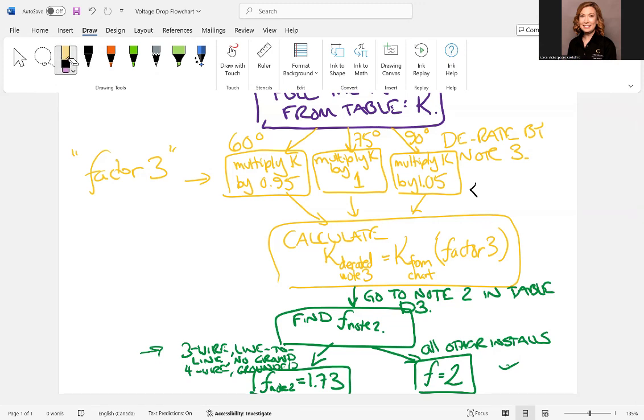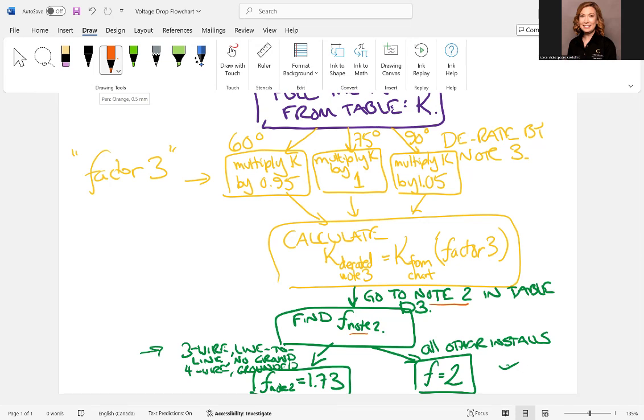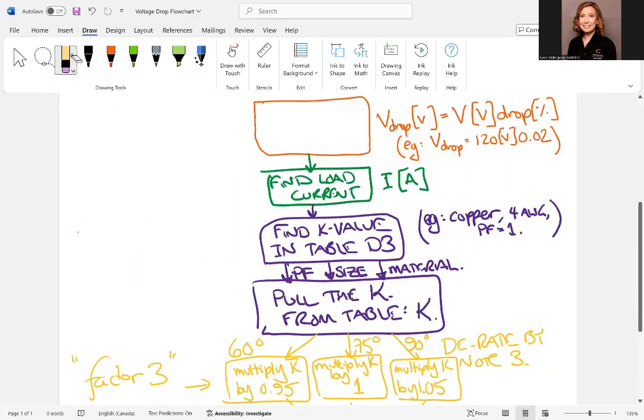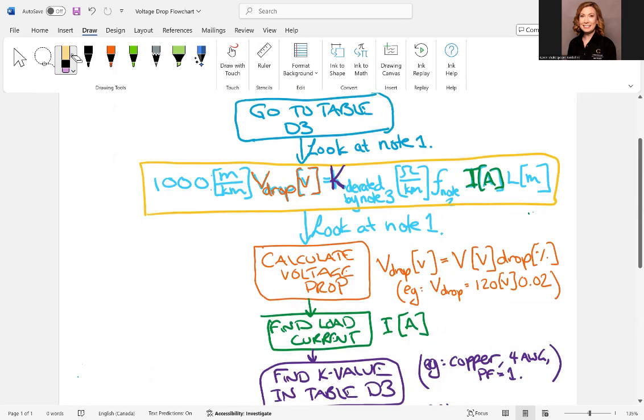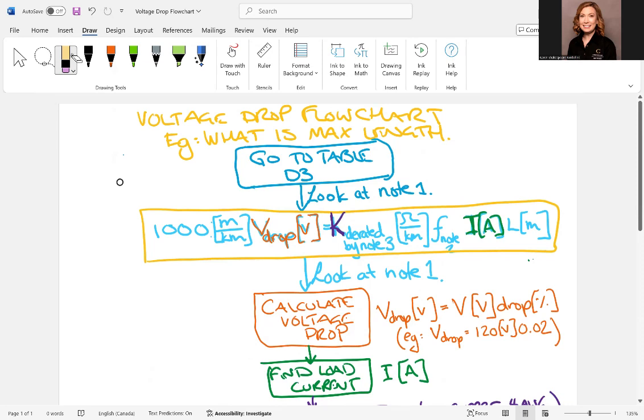So now that we have K and it is derated, we go to note two in table D3. And note two says that if it is three wire, line to line, no ground or four wire grounded, then F in our equation will be 1.73. All other installations, F is two. Usually F is two. And that's how we do the voltage drop calculations using table D3 in the 2024 electrical code.